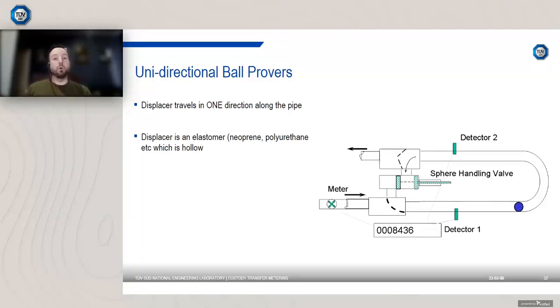I'm not going to talk about every single type of pipe prover, but a good example is a unidirectional ball prover. This is where you've got a displacer that travels in one direction along the pipe. This displacer is usually an elastomer, like a neoprene or polyurethane ball, and it's hollow. What you do is you inflate this displacer to about 2 to 5% more than the internal diameter of the pipe. Why is that important? It's important that the displacer creates a seal against the wall of the pipe because you don't want fluid moving from the upstream to the downstream side, because that affects the quality of the prove. It's important that the displacer is maintained, because if it is of poor quality or becomes damaged, it will allow flow to pass from the upstream to the downstream side.